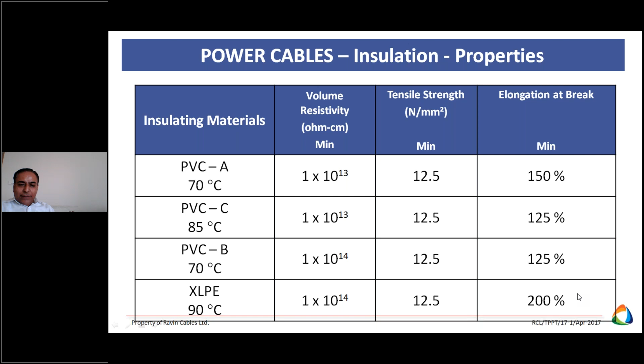Volume resistivity is better in case of XLPE cables. XLPE operating temperature is 90 degrees centigrade, PVC is 70 degrees centigrade. Continuous conductor temperature not exceeding 70 degrees centigrade in case of PVC, and not more than 90 degrees centigrade in case of XLPE. So the insulation dielectric properties are better than PVC. Mechanical strength is almost the same, but elongation is better in case of XLPE. Now we are coming to some comparison.